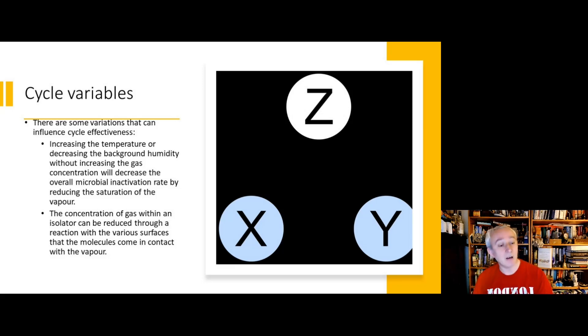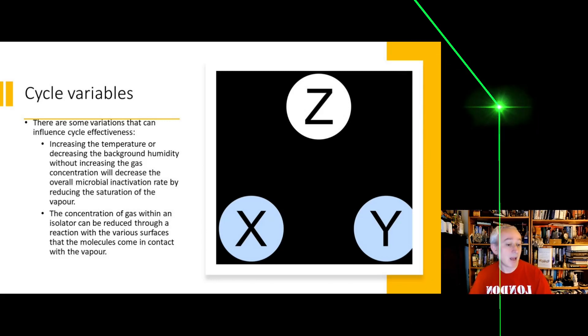So when we're running hydrogen peroxide vapor systems, we need to check critical parameters, and we can add to these the time as well as the concentration, temperature, humidity, to make sure all of those are right. Much like running an autoclave, there's a series of key parameters that need to be assessed.